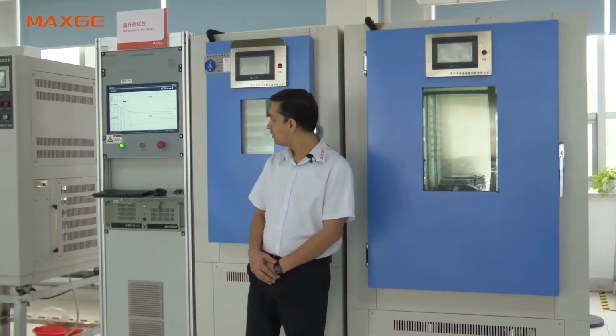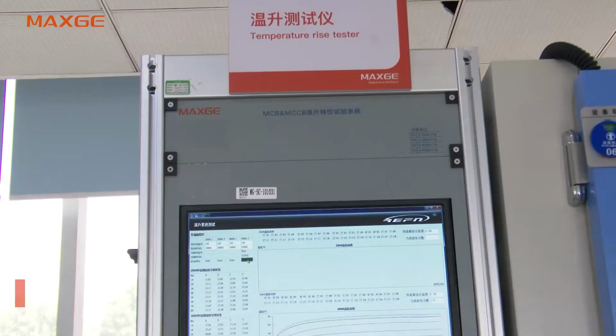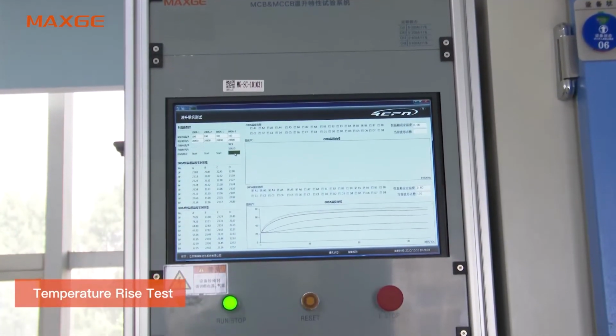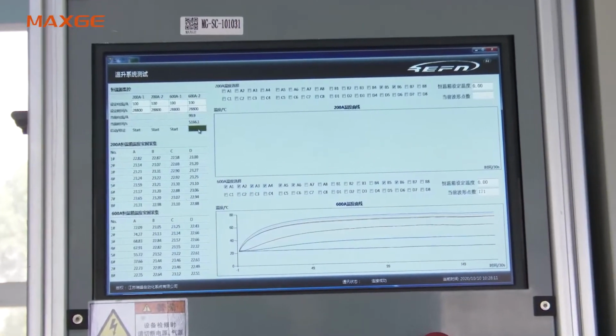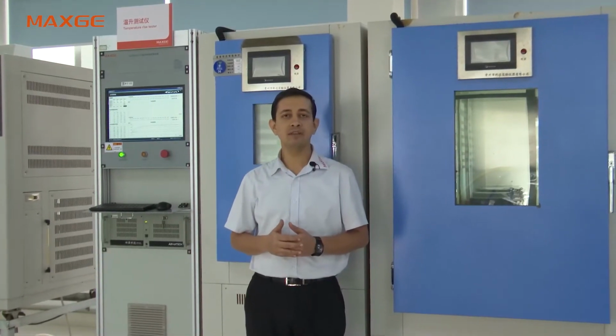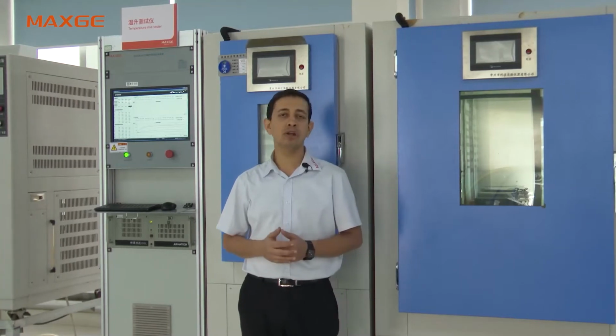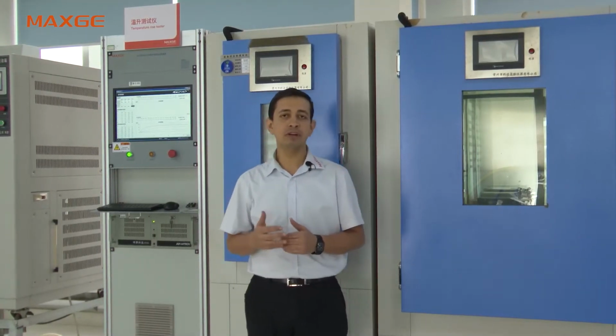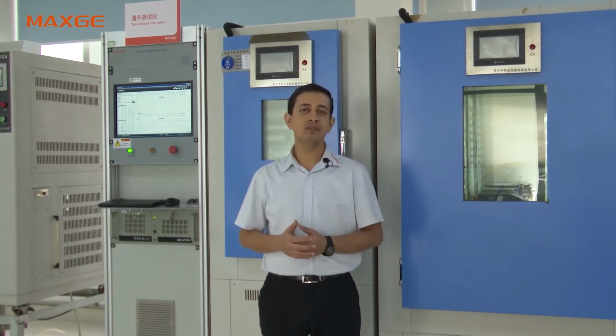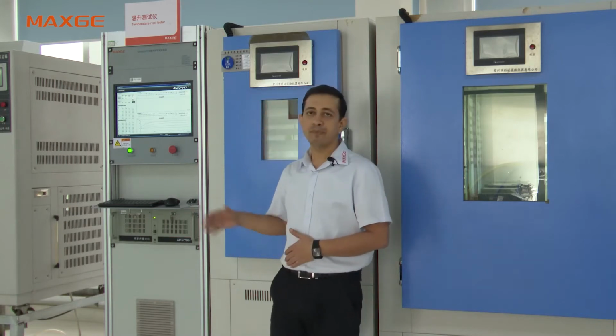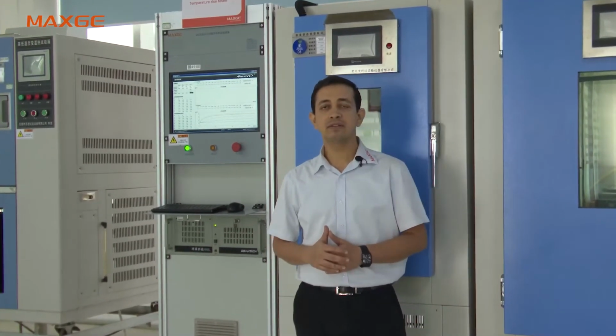Now we are standing near the temperature rise testing machine. Here you can see the test is already going on. This test is very important as far as MCCB or MCB performance is concerned, because once the cables are connected, the temperature at the terminal should not exceed the specified limit mentioned in the IEC 60898 Part 1 standard or IEC 60947 Part 2 standard. These are the specification limits mentioned in the standard. As per IEC 60898 Part 1, the specification limit is 60 K, whereas IEC 60947 Part 2 says 70 K before electrical endurance and 80 K after electrical endurance. So this test is very important as far as the standard is concerned.